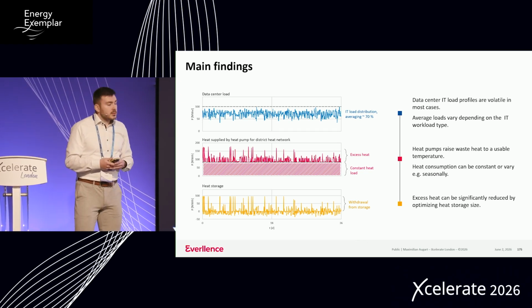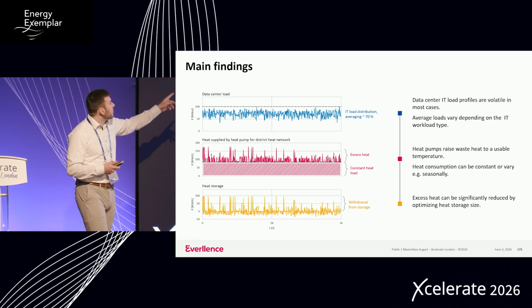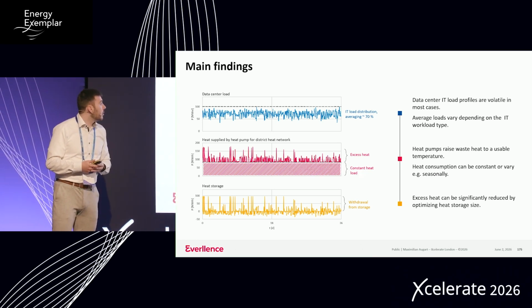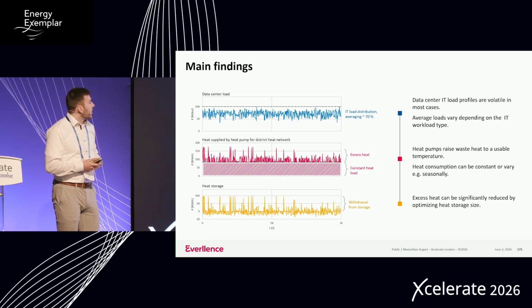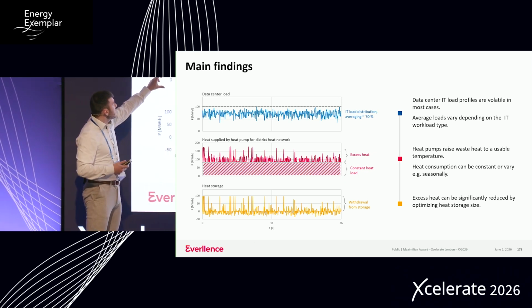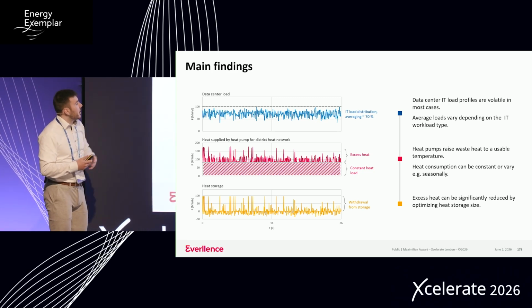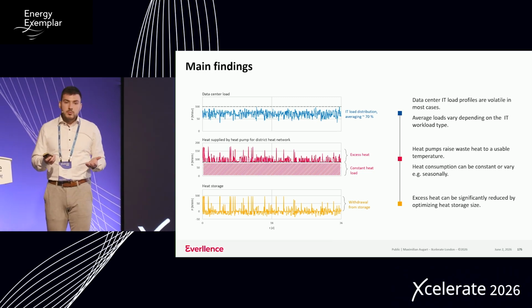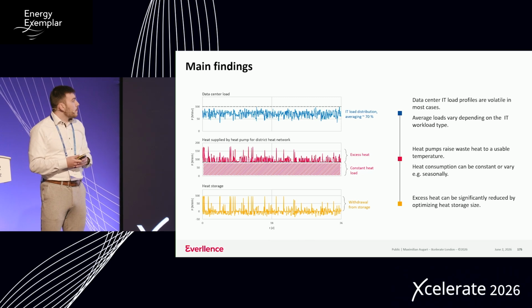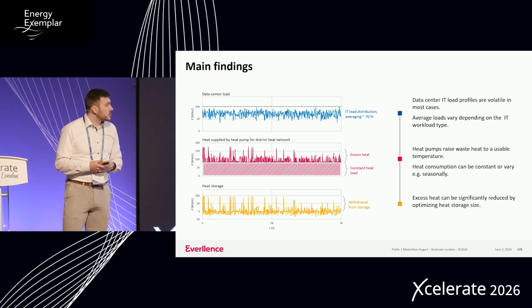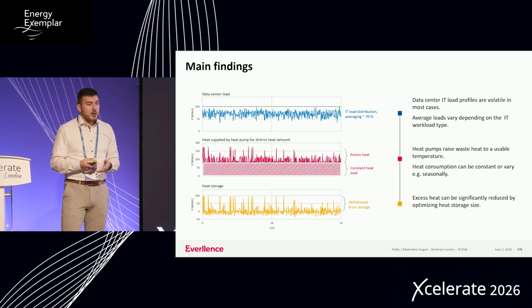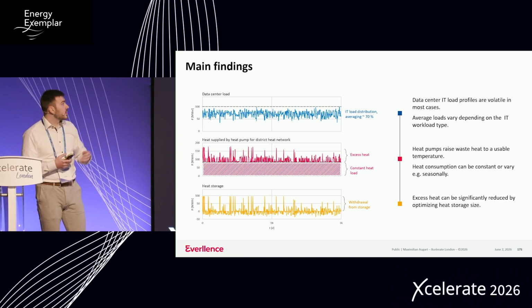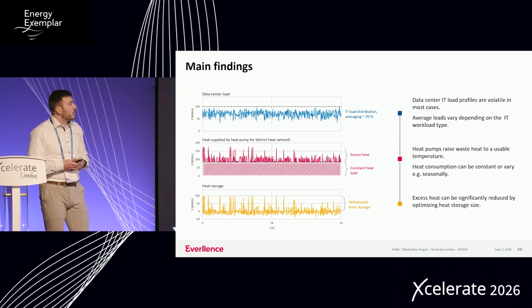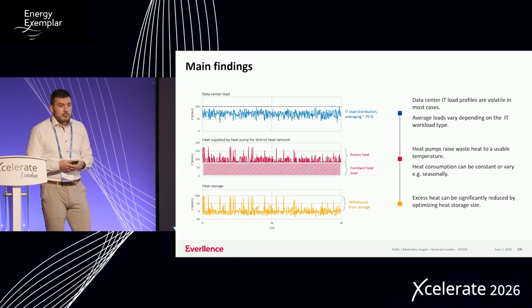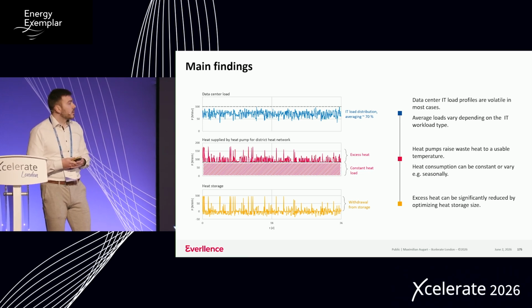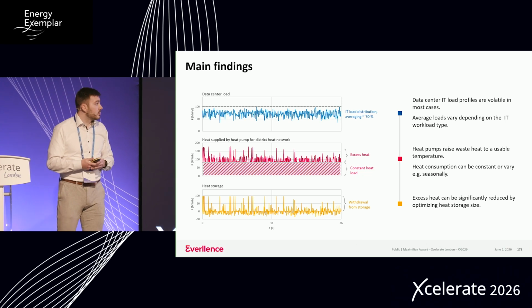This gives rise to the heat supplied by the heat pump. In this section I've got a constant heat load, and everything above is excess heat that I'm either able to use or need to cool away. A good thing is that the heat pump raises the heat coming out of the data center, maybe 30 to 40 degrees Celsius in this case, up to around 88 degrees, though it can be even higher, for use in a district heat energy system.